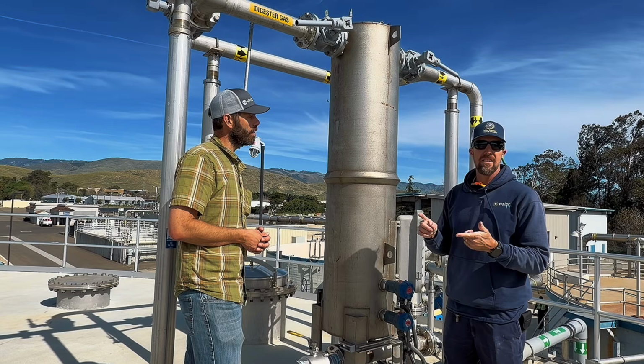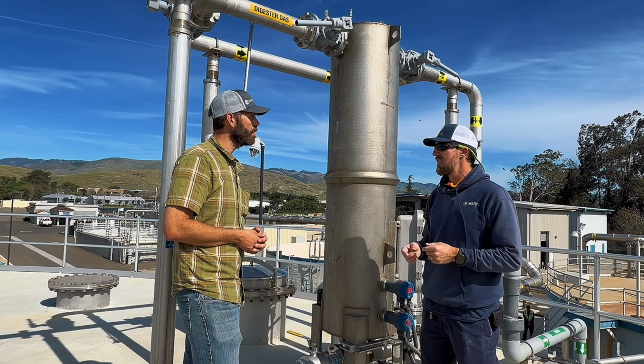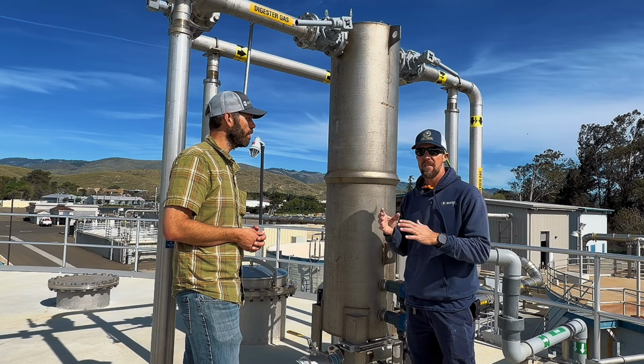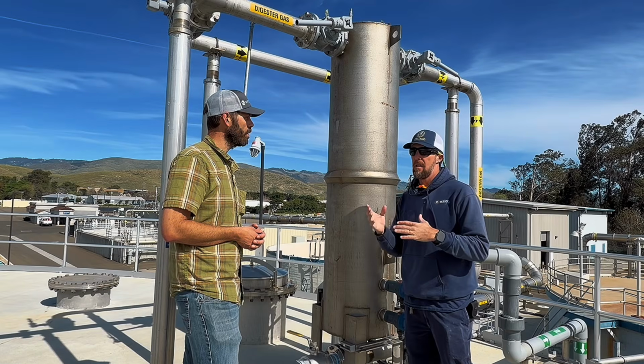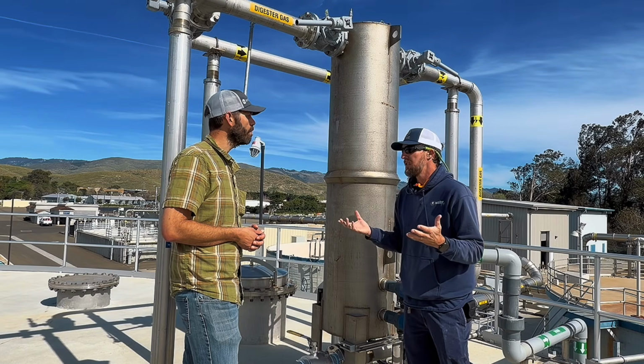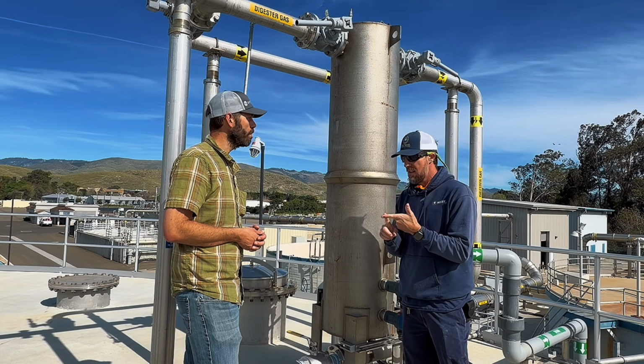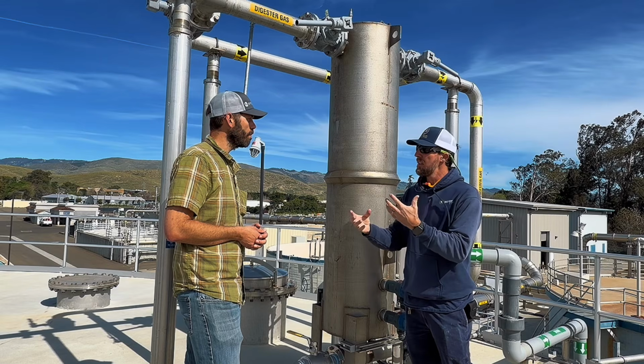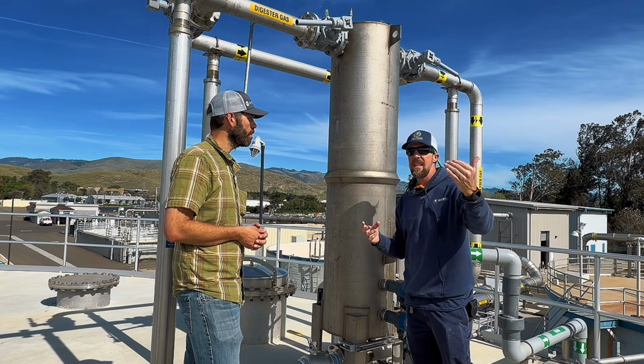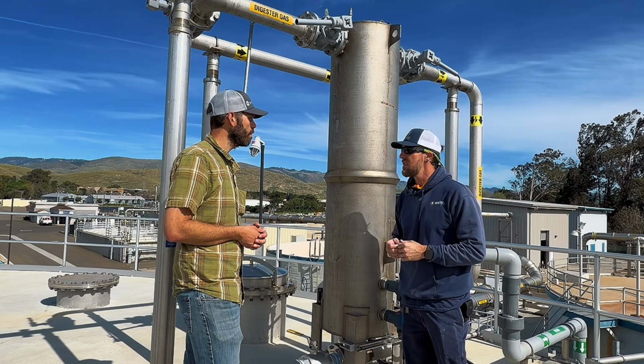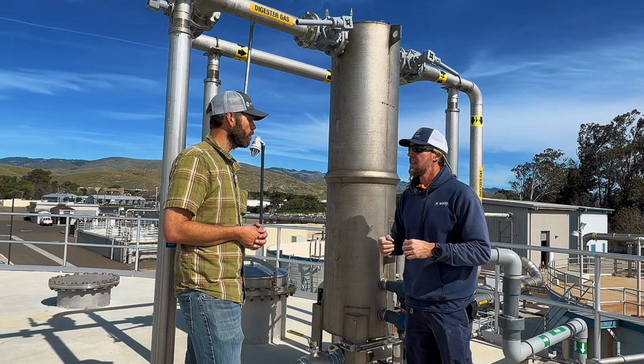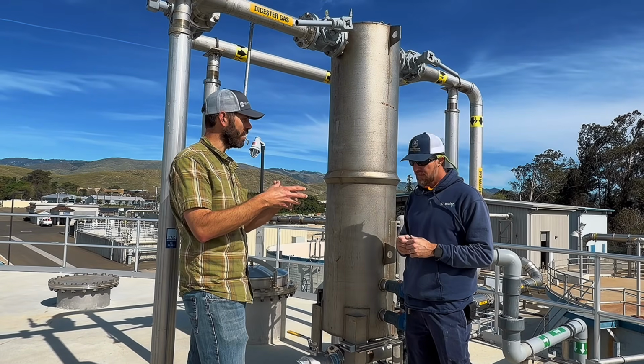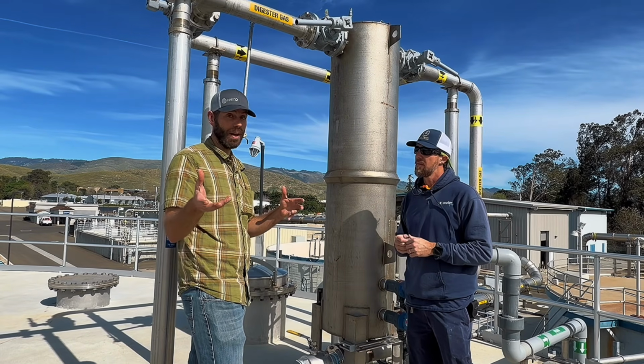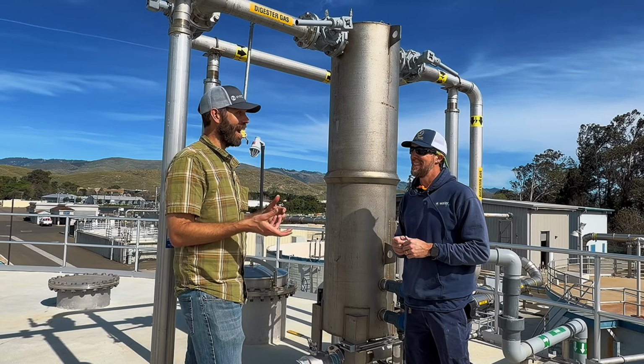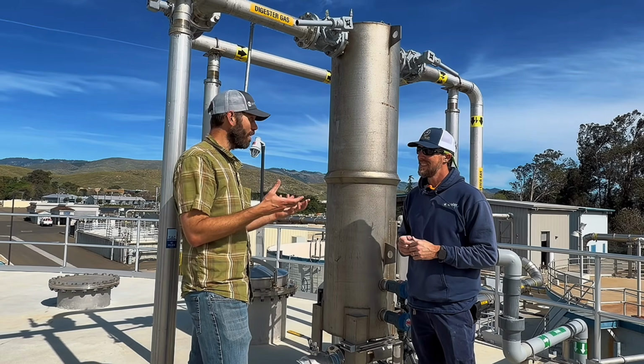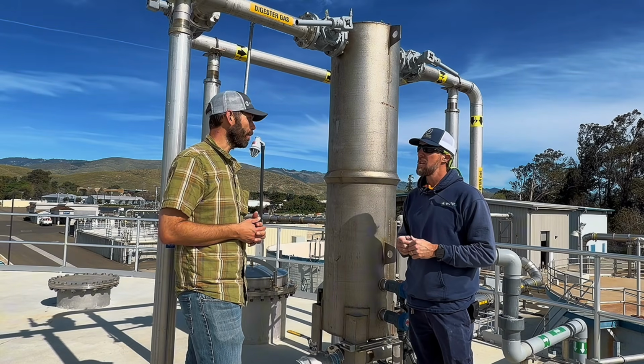Yeah, the cogen unit at this juncture is producing 150 kilowatts. So it offsets our PG&E electrical bill, huge savings there. And to close that loop, it affords us heat for our heat exchangers to heat the sludge within the tank, so that you can keep that constant 98 degrees. And that's the mesophilic range, by the way, if you're taking an exam. Yeah, there you go. And if you have too much, you flare it off, right? Of course. Find that balance, right?